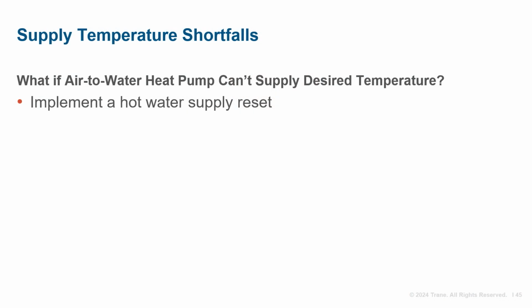supply temperatures. One of the common issues that designers run into when designing an electrified heating system is that the air-to-water heat pump or water-to-water heat pump can't make the required hot water supply temperature. So what options do you have? First, implementing a hot water supply reset, often based on outdoor conditions, limits the number of hours when higher hot water supply temperatures are required.